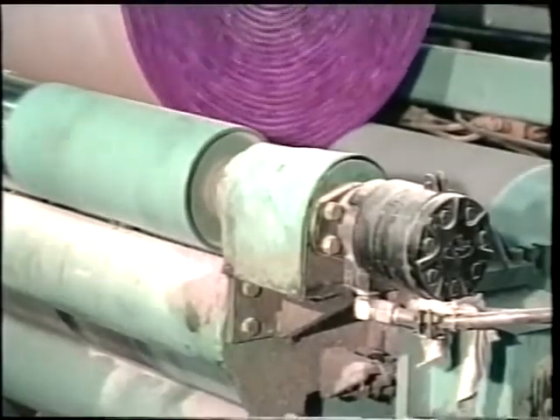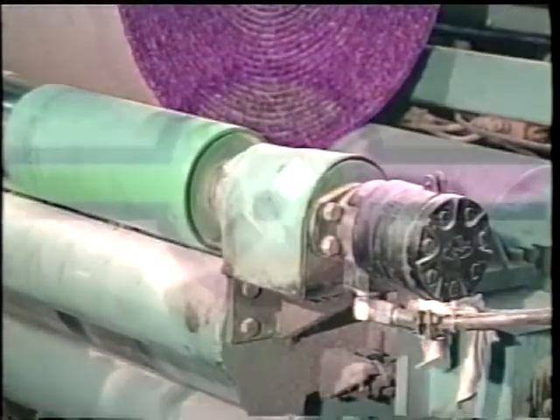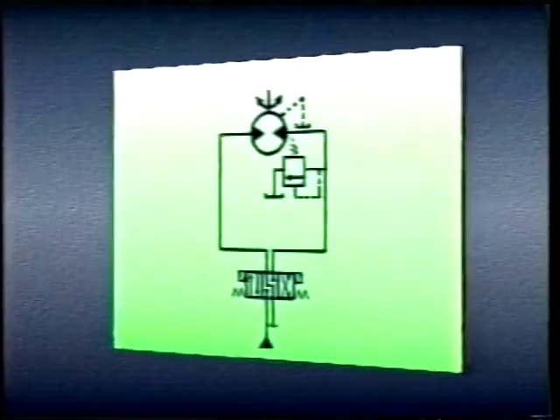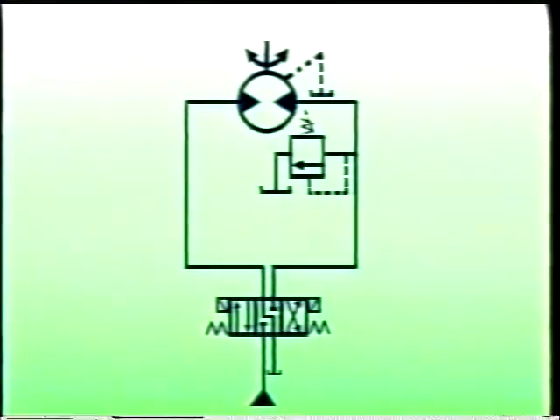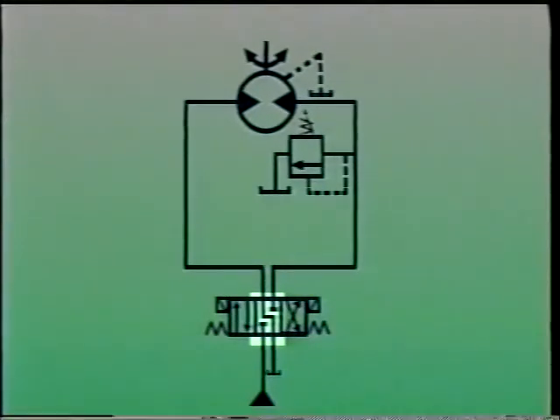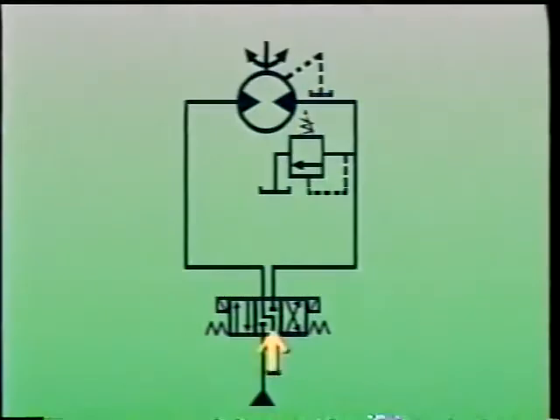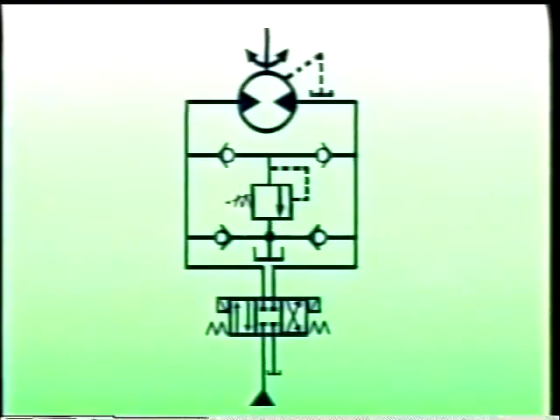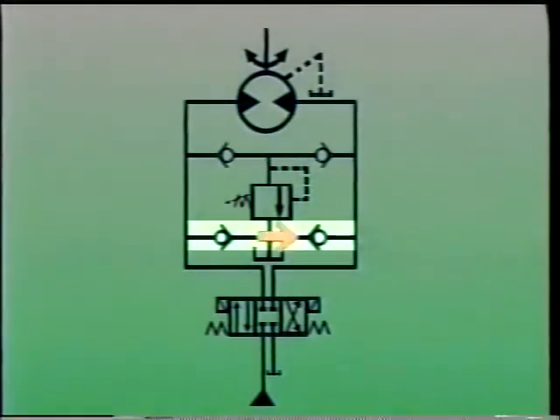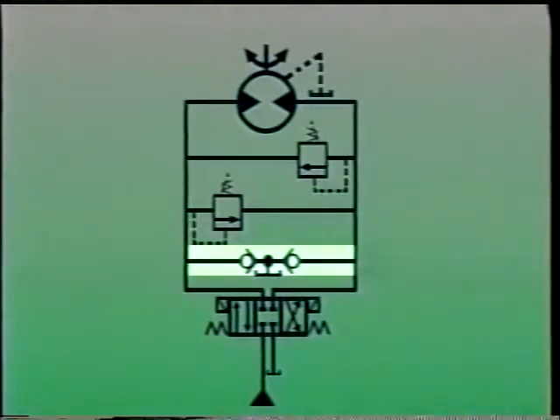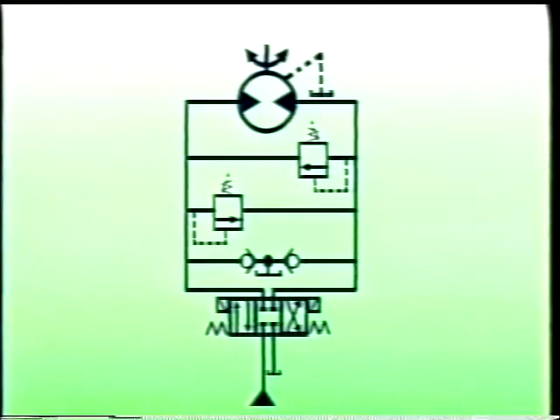Whenever hydraulic motors are braked, some method must be used to make sure fluid is available at the motor inlet, otherwise the motor will cavitate and may be damaged. Three methods are generally used. One method uses a directional control valve in which the center condition connects the motor's inlet to tank, so back pressure brakes the motor while fluid flows from tank preventing cavitation. Another common method uses make-up checks — very low pressure check valves which allow fluid to flow out of the tank and into the motor. The last method uses crossover relief valves, where one or the other discharges fluid to the motor inlet depending on which way the motor is turning; make-up checks are still required since some fluid will be lost through the motor drain and across the directional control valve.